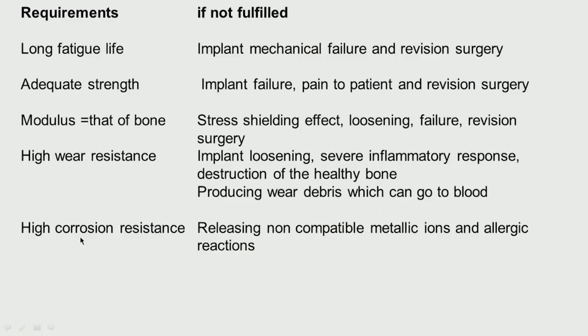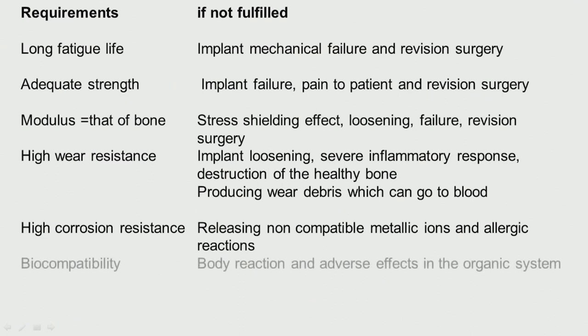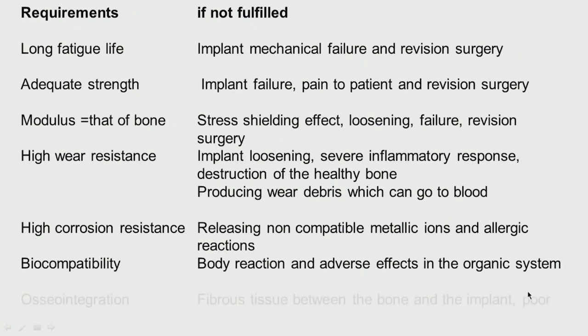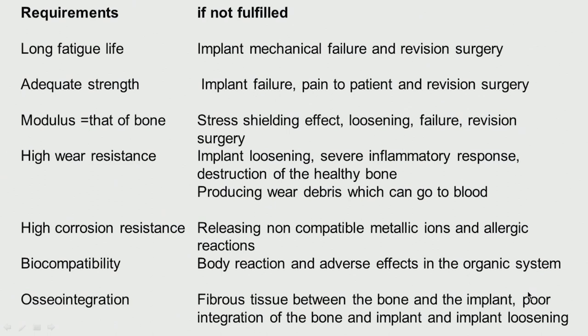High corrosion resistance is needed because low resistance leads to release of unwanted metallic ions. Biocompatibility must be fulfilled to prevent adverse reactions. Osseointegration is also critical — if it does not occur, fibrous tissue can form between the bone and implant, leading to poor integration and implant loosening.